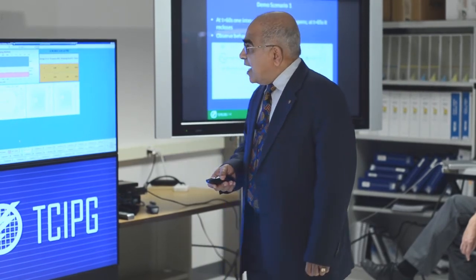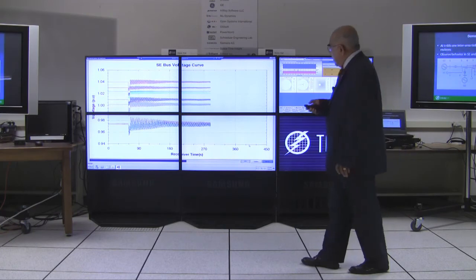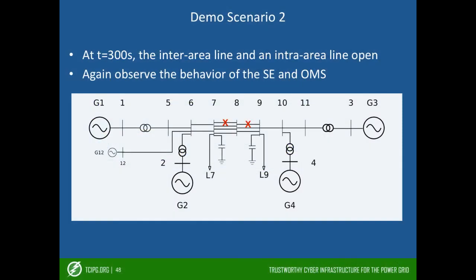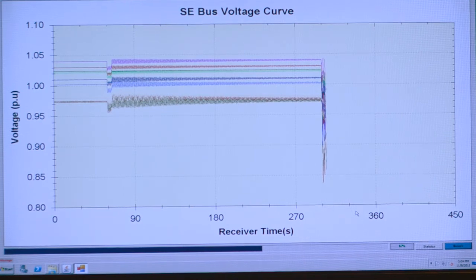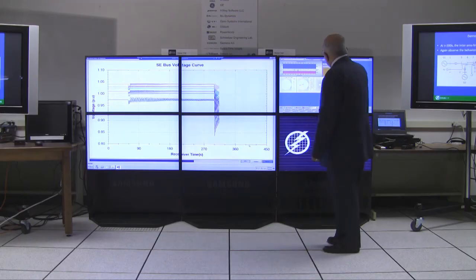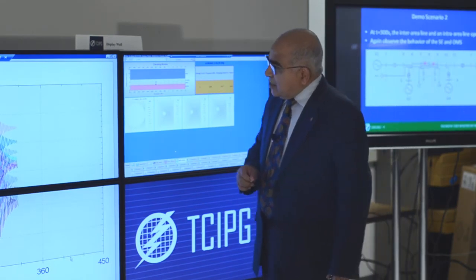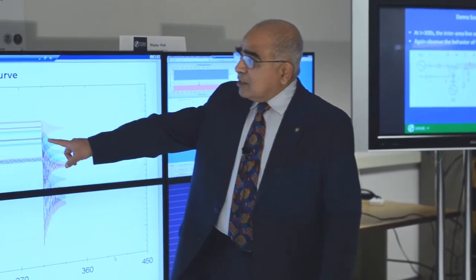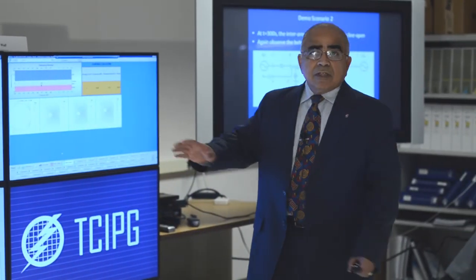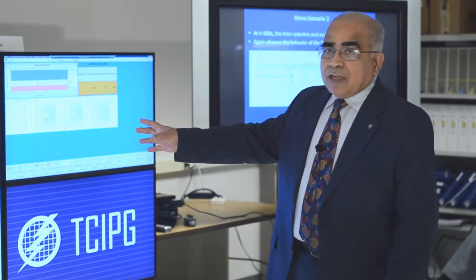It was lightly damped but still damped, so you would not worry too much. Then the next line opens — where that next cross is — and suddenly you have a big dip in the voltages. You watch the oscillation monitor, and the 0.7 Hz oscillation is being picked up, but again it is damping out — in fact with a higher damping ratio than the first disturbance. This represented about five minutes of real-time simulation.